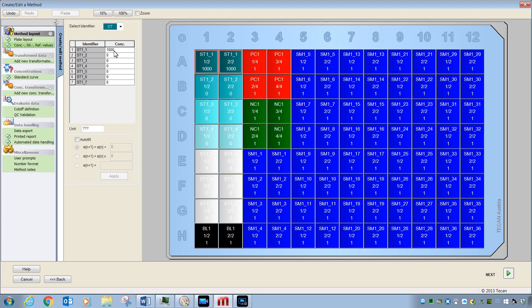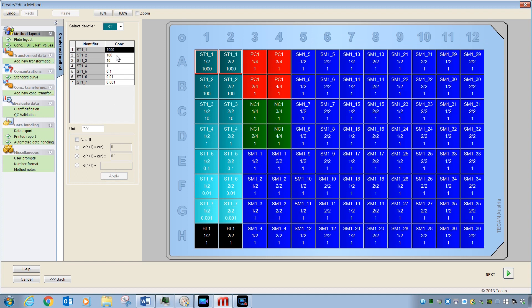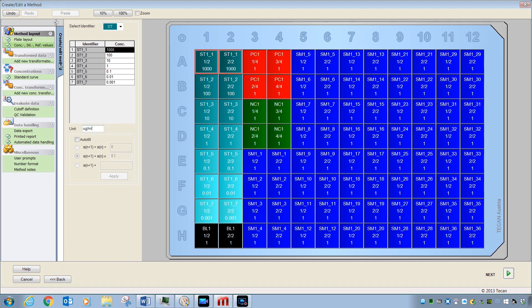Alternatively, you can type the number here and use this autofill feature. It's convenient if you have lots of different dilutions or a specific series of the dilution that can be accomplished via a mathematical formula like this. Here I'm entering point one and when I hit Apply, it automatically dilutes or divides these by ten. And you can see here in the screen then, it puts those dilutions in the well and also uses a color scale to help visualize the dilution. You will also want to type some text here in the Units field. Leaving this field blank will prevent the software from calculating your concentrations.